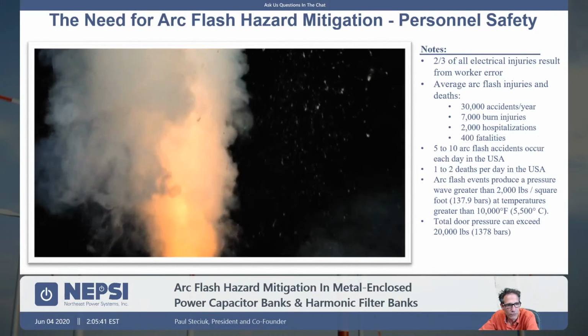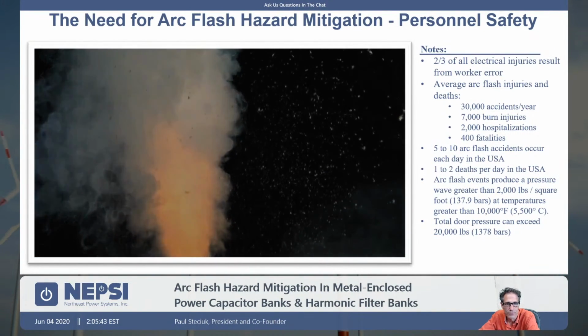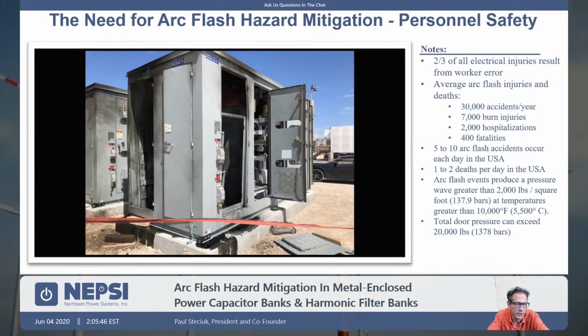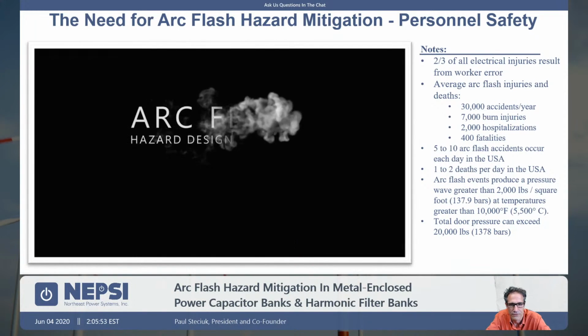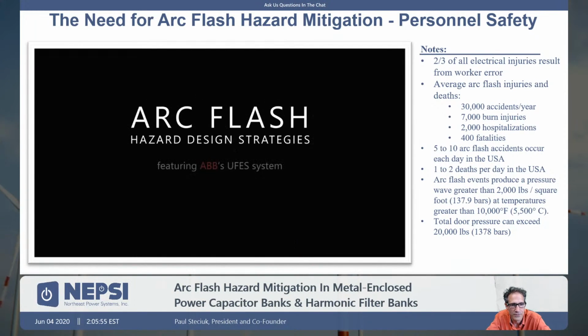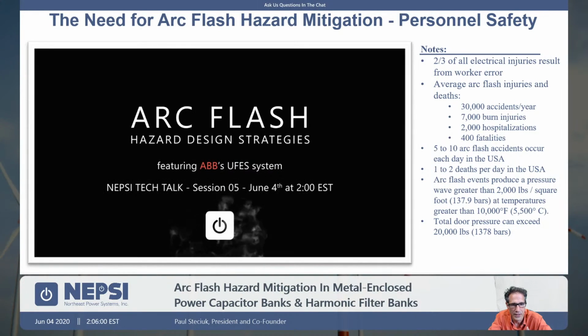So this was a teaser video that we actually put together to get more participation for this Tech Talk session. And what this video clearly shows is that an arc flash event can be quite significant. It bends the steel, it expels a significant amount of gas, and it takes the equipment out. In this particular case, it was an event that occurred within our equipment. It was a CPT failure, and it was quite catastrophic. So whenever thinking about arc flash mitigation, think about these types of things.